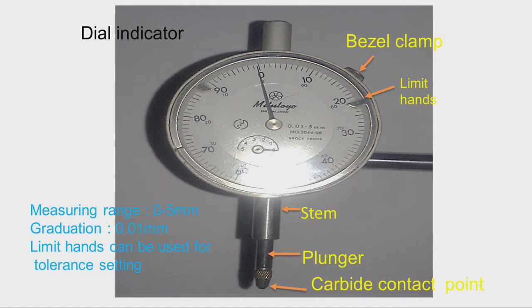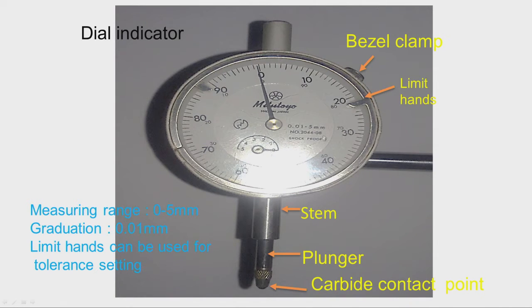First, let us discuss about dial indicators. This figure shows a commonly used dial indicator. We can see the various parts: the bezel and bezel lock, and the dial. There is a bigger dial and a smaller dial. The resolution of this dial is 0.01 millimeter, and for each revolution of the big pointer, the small pointer moves by 1 graduation.